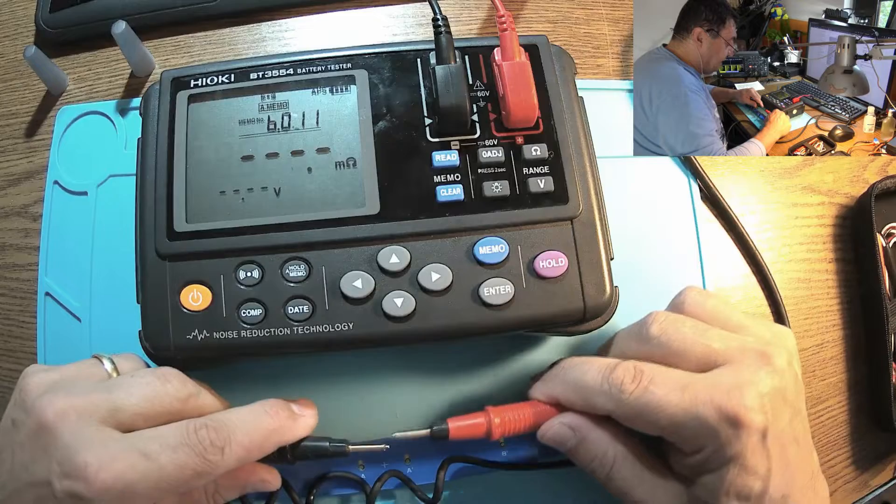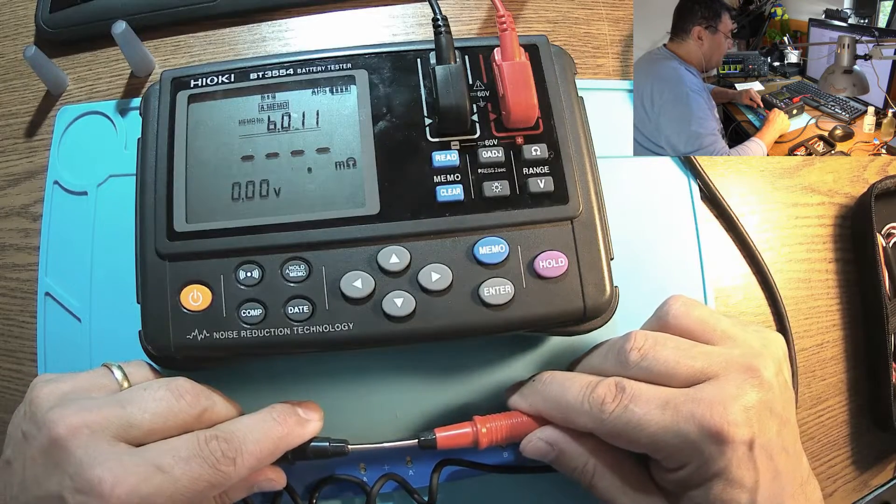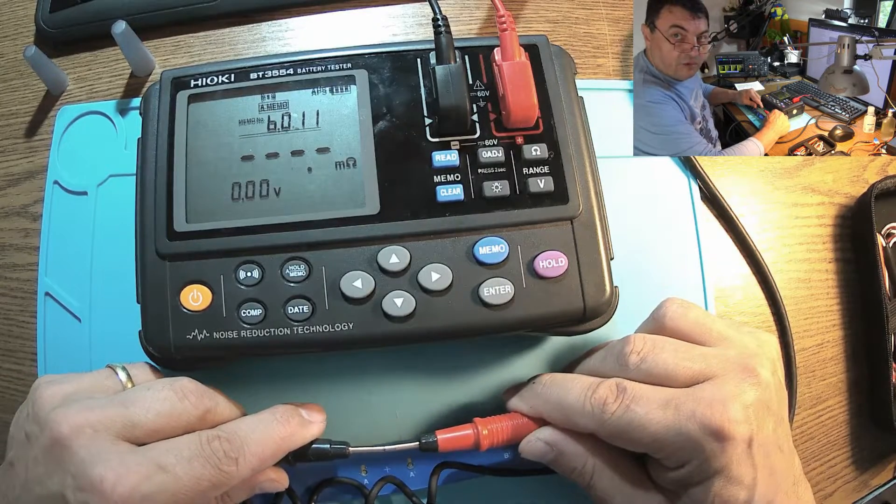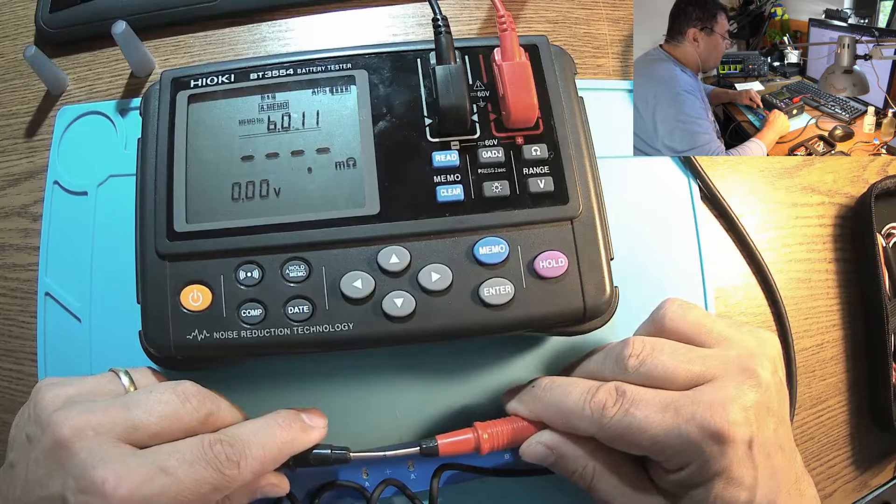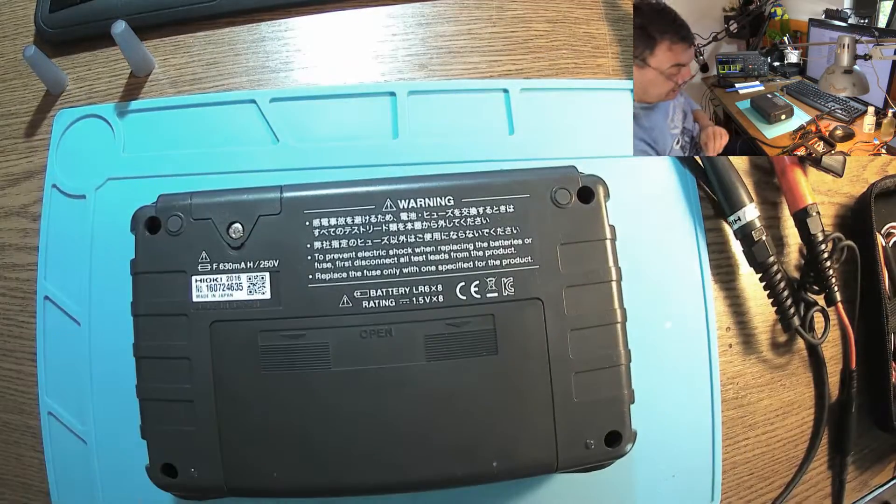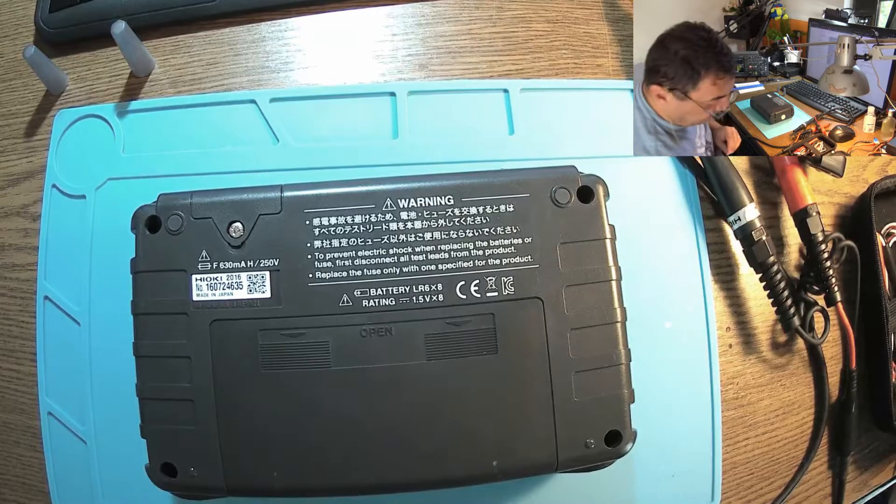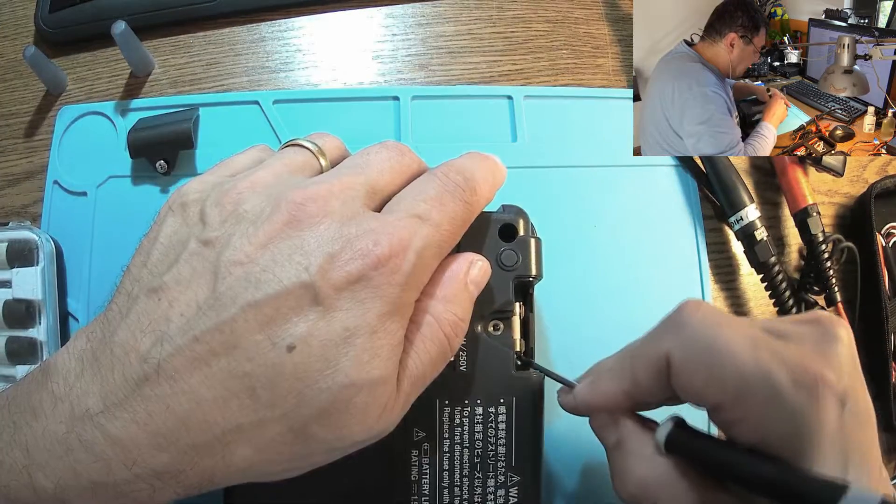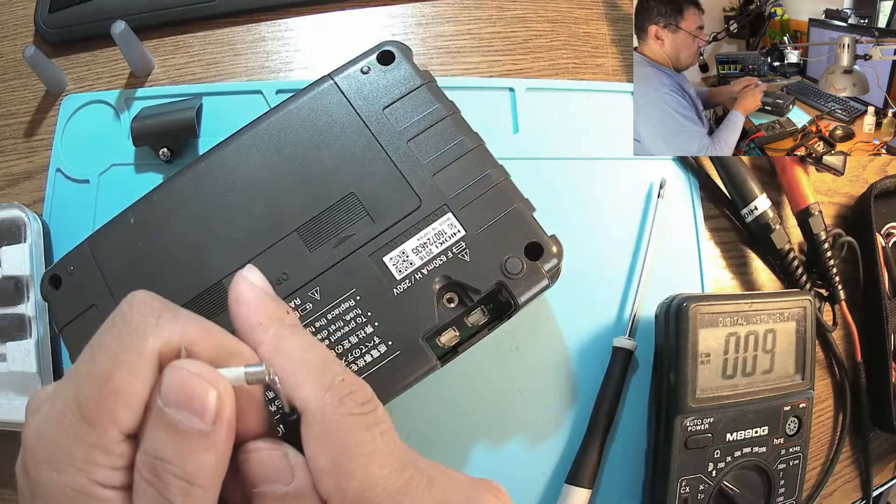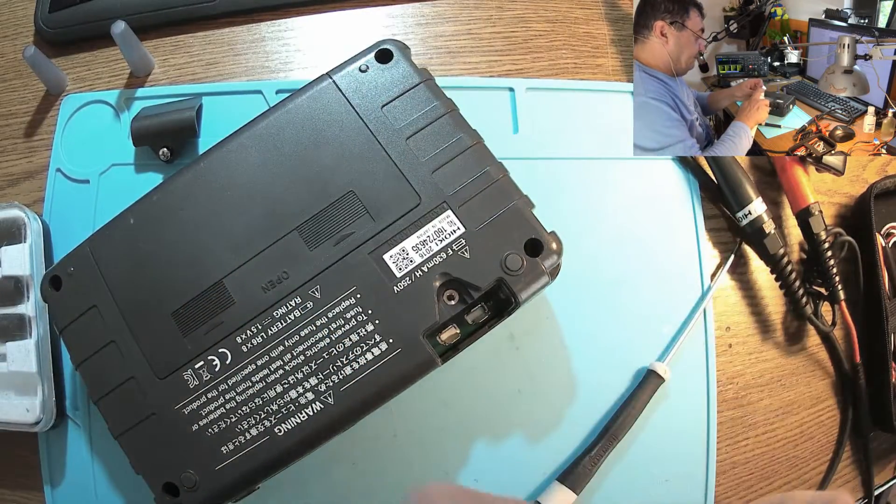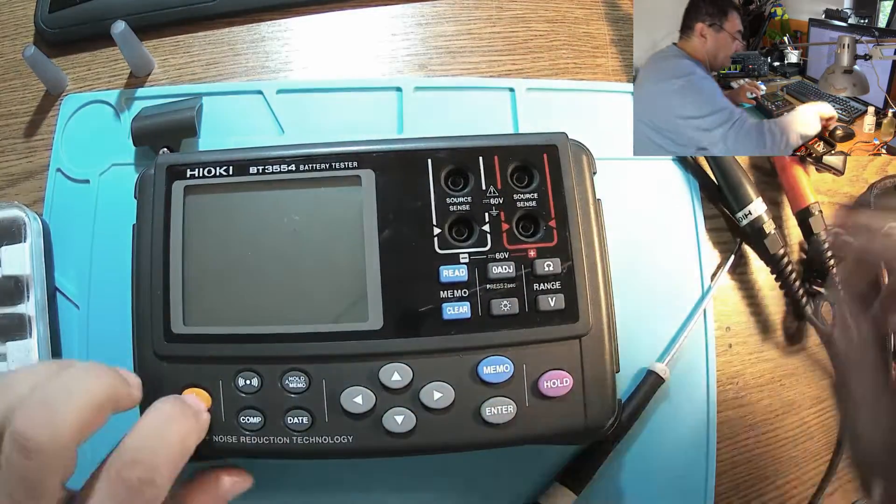The measurements with this kind of machines are done in four points. It's not only a voltage applied here, but also a frequency of 1 kHz. And we should start checking the fuse, but I'm pretty sure the fuse is okay. Yeah, here we have a fuse. Let's clean it a little bit. Yeah, it's contact spray. Okay, let's go back.